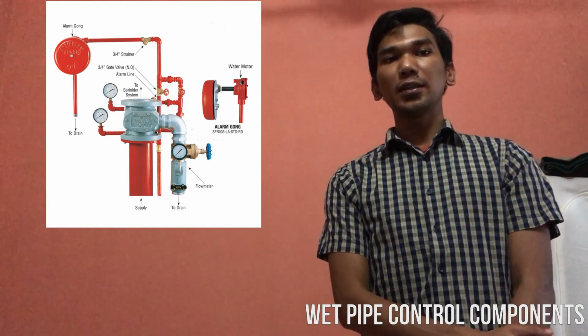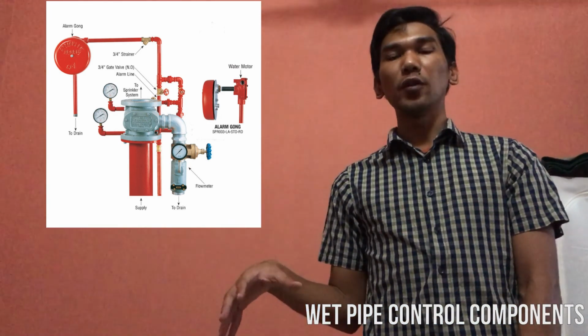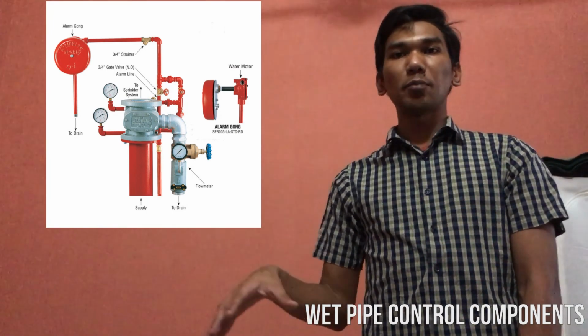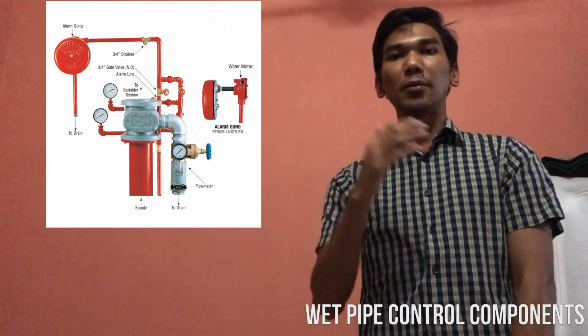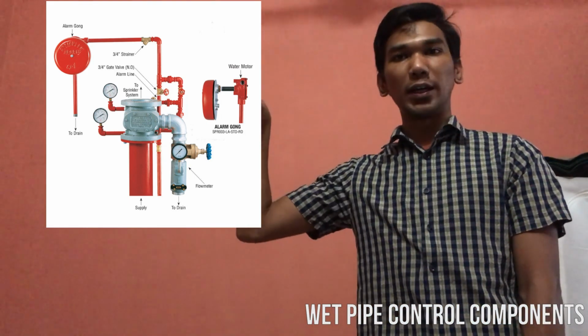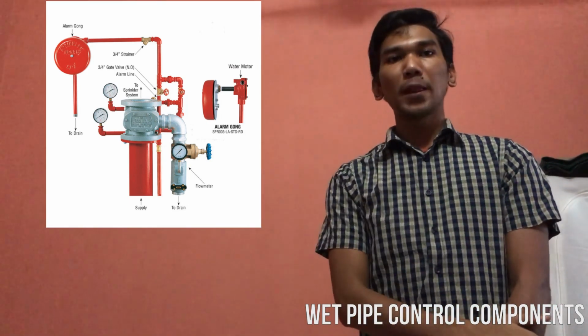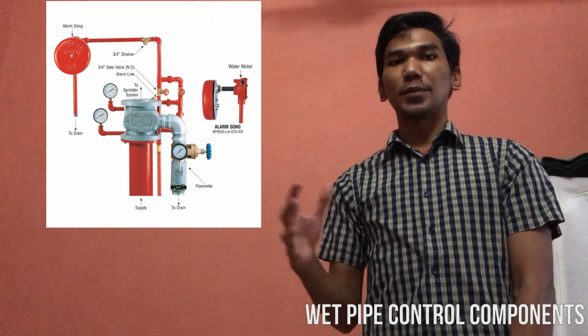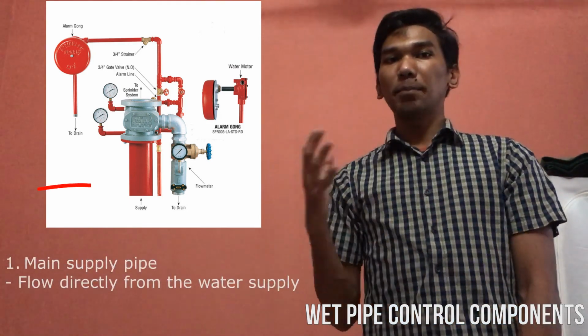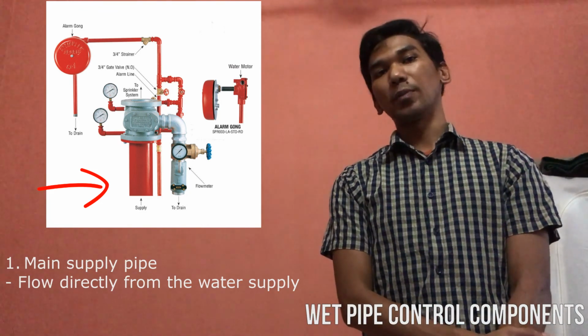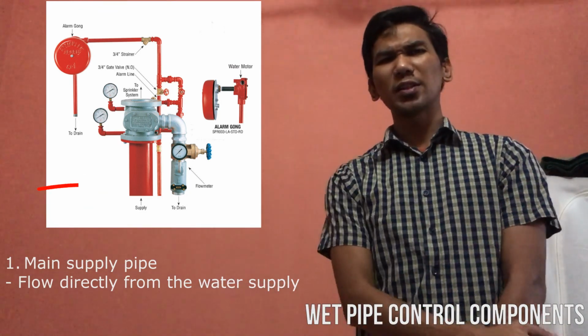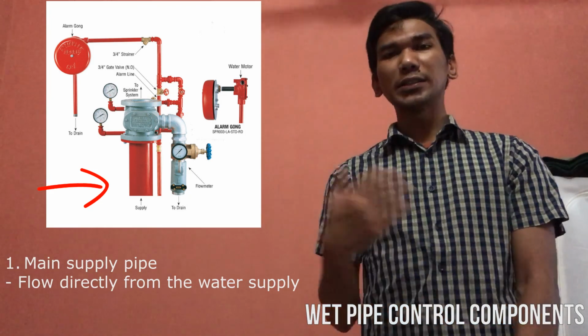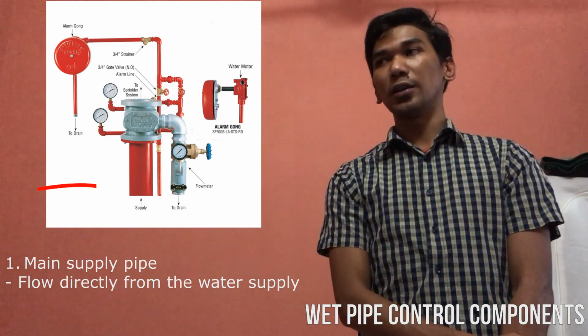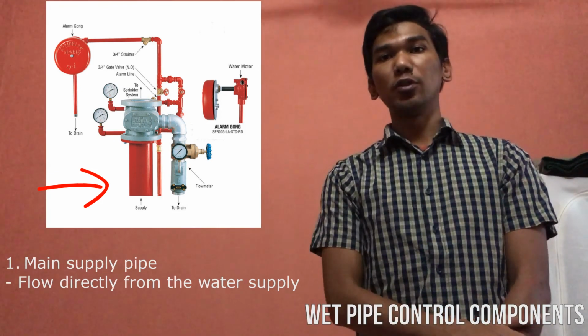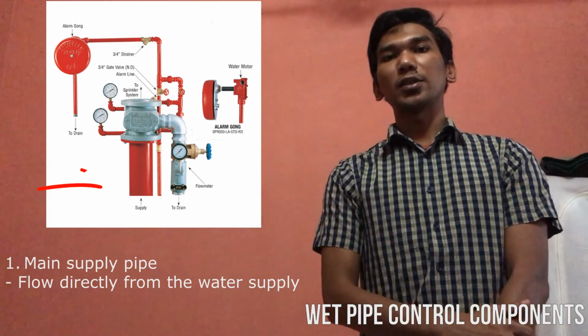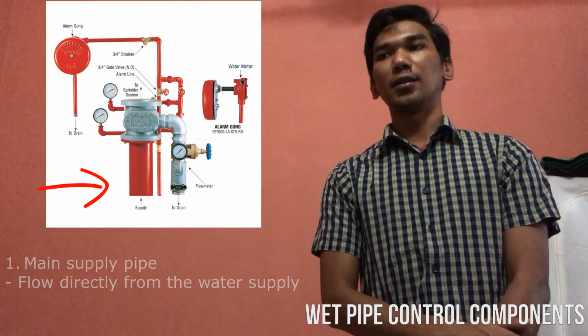So as we can see, this is the water pipe that flows from the water supply and goes through the pipe that flows to the sprinkler. So the first one is the main supply pipe. The main supply pipe flows directly from the water supply. Usually the water supply is from the water tank and also the reservoir from outside of the building, if the building cannot support the size of the reserve tank.